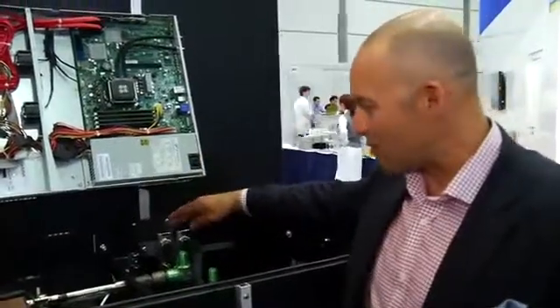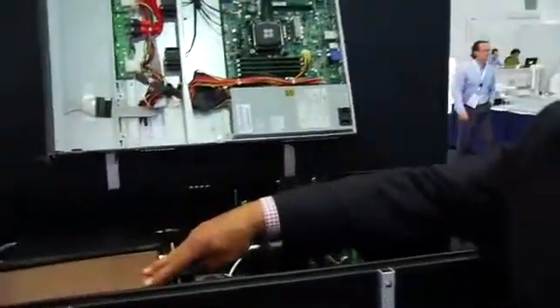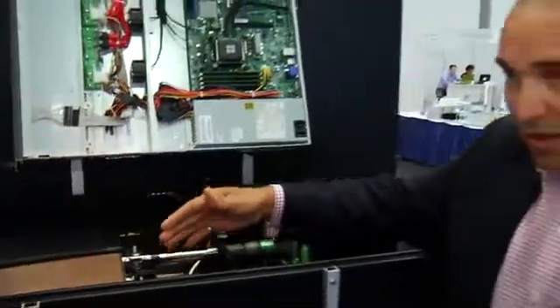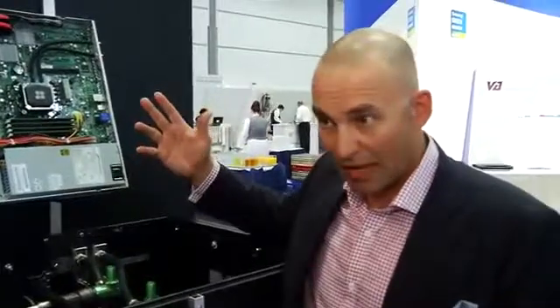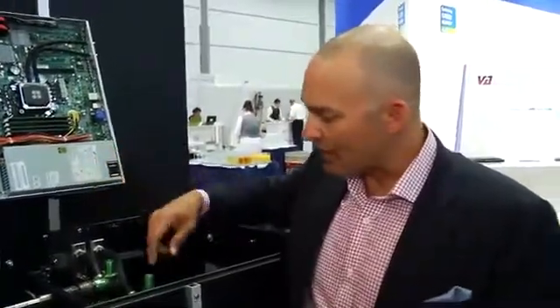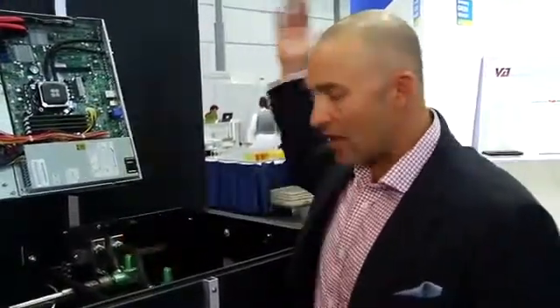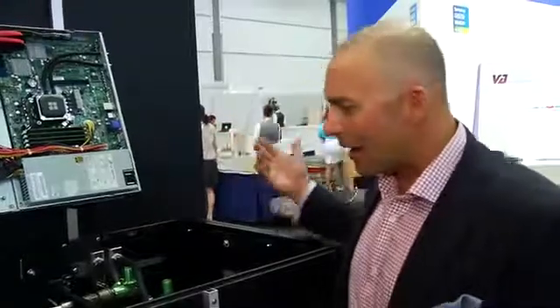That's exactly right. We have our product called a CHx, coolant heat exchanger. Instead of the manifolds connecting up to a radiator up top, we're now connecting to a liquid-to-liquid heat exchanger. The heat comes back from the CPUs to a stainless steel plate heat exchanger, very high capacity, easily capable of 40 kilowatts plus. Then we transfer that heat into the facility liquid, which is exhausted outside the building. By using that system, our efficiency is incredibly high since we don't need any compressive air conditioning - the hot liquid can be recycled into a building or just dissipated using dry coolers outside.